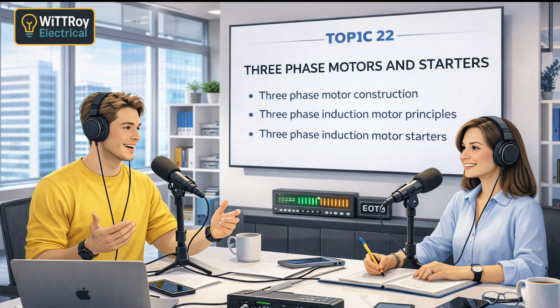Exactly. And because they're powerful, they need proper starters, not just to start them, but to protect them. Like overloads, phase failure, and all that. Yes. Overload protection looks after the motor windings. Short circuit protection looks after the cables and equipment. Phase failure and phase reversal protection stop serious damage before it happens. That part makes more sense now. Good. We also looked at different starting methods. DOL starters are simple but draw a very high starting current. Star delta, auto transformer, and resistance starters reduce that current in different ways. And modern electronic starters give smooth, controlled starting. So choosing the starter really depends on the motor and the load. Exactly right. That's the big picture.